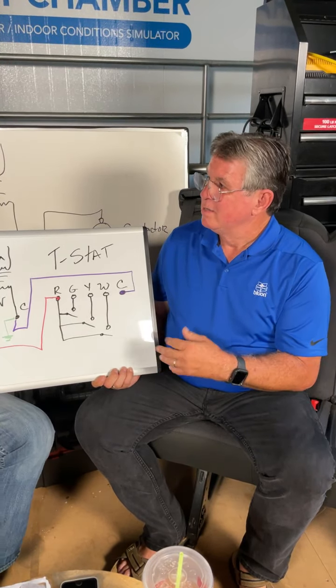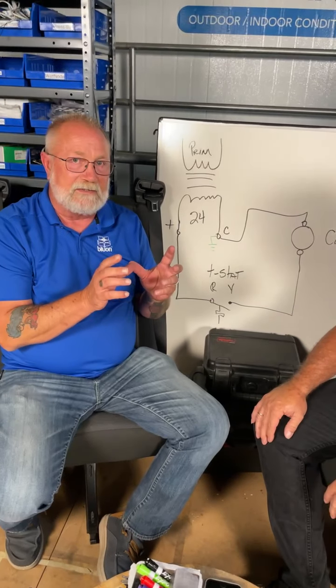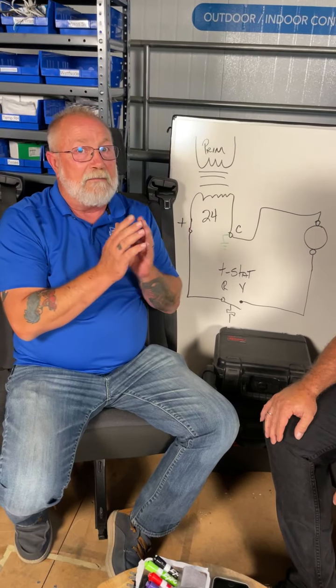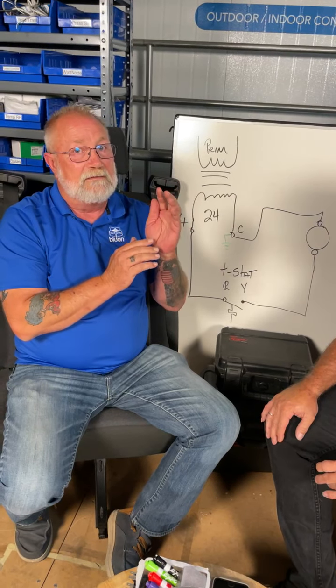Same principle. If you see your primary voltage transformer 24 volts, to help Mikey out, I'll put the little ground in there. So there's your chassis ground. Now, a lot of guys when they're doing this, they talk to us and they're going, I'm reading 24 volts between R and Y, and my cooling's not coming on. Well, here's one reason why. If you read from R to Y and the thermostat is not closed, then you're going through the contactor coil back to common. So you would read 24 volts.